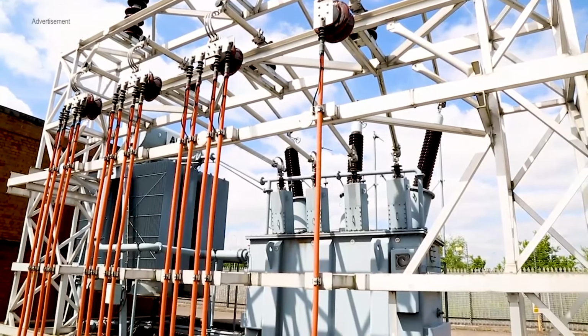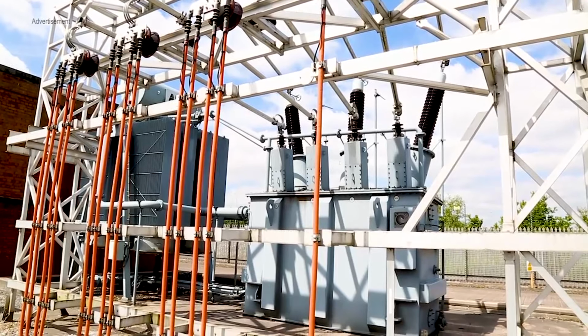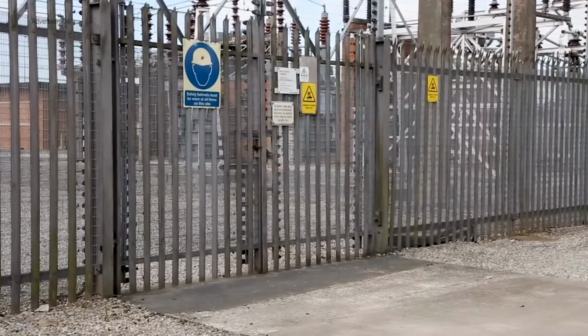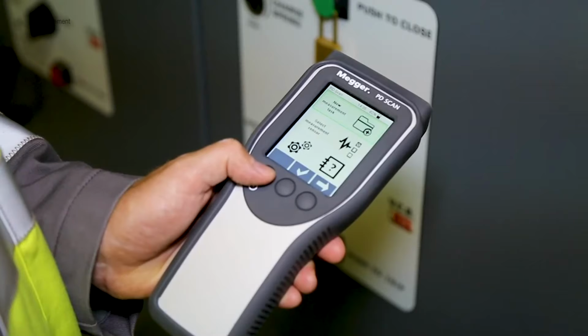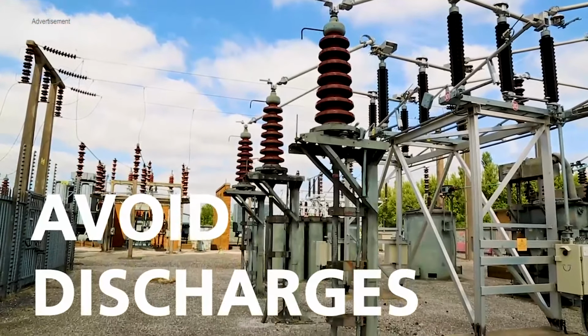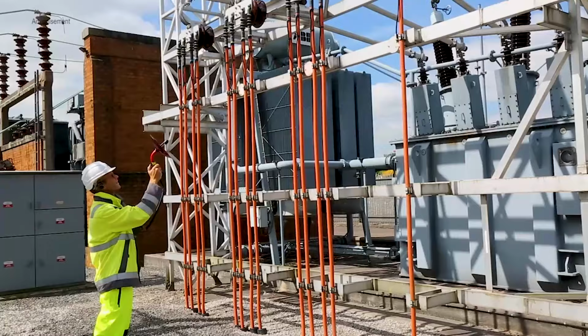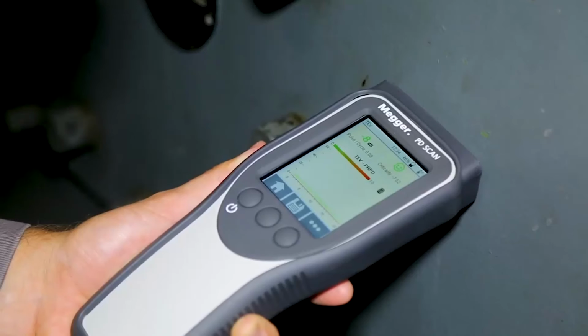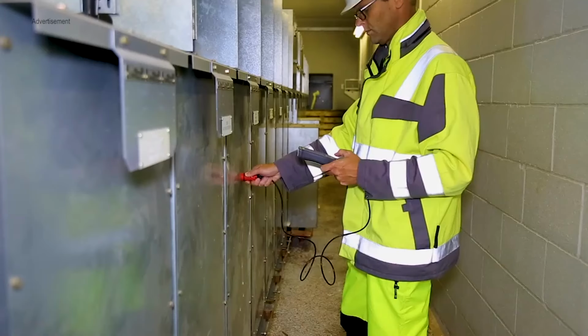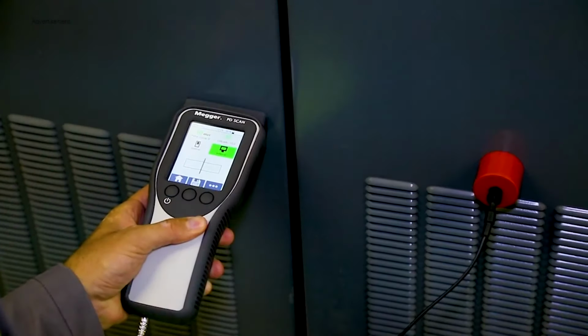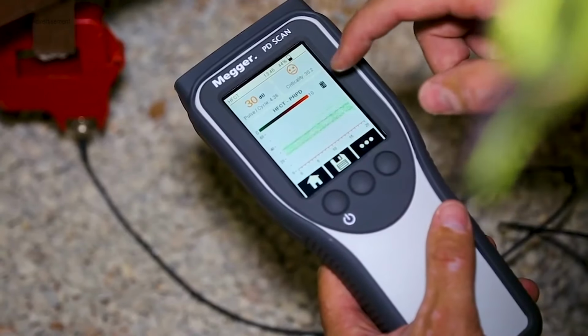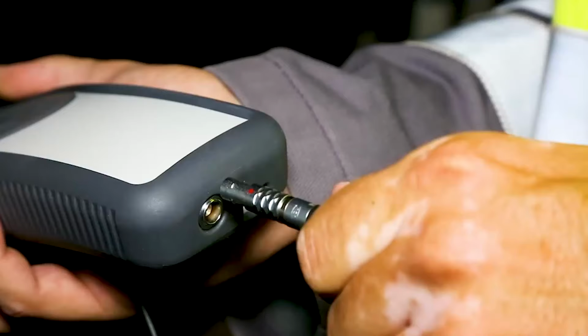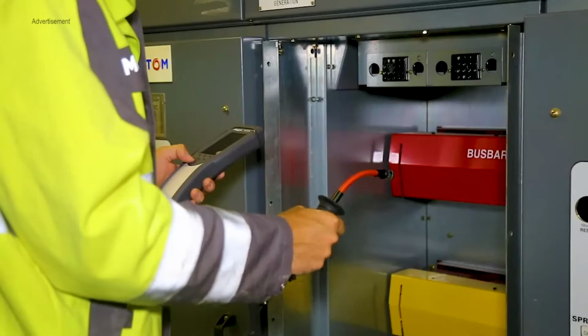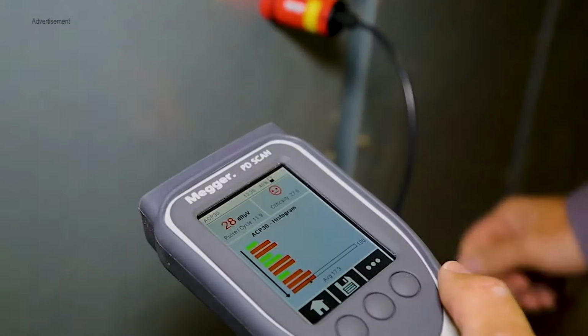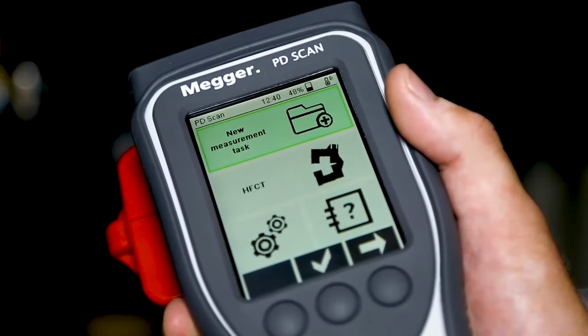Partial discharge is a warning sign of insulation failure. This can also lead to potentially dangerous conditions for substation staff. Megger's PD scan is designed to detect partial discharges to identify faulty equipment before it fails. With its 6 independent and unique sensors, this handheld device is the best for helping you find PD faults quickly and easily. Whether you're working in high or medium voltage substations, to help you find PD faults efficiently, it has acoustic, TEV, and HFCT sensors.